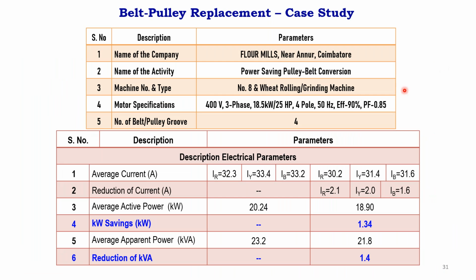This is the simple case study we conducted in a flour mill, which is a wheat rolling mill with a 25 HP motor, which has a 4 belt and 4 groove configuration. This side of the table is the before study, and this is the after study. Before, it took an active power of 20.24 kilowatt, and after changing the belt and pulley with the cogged belt, we achieved a small saving of 1.34 kilowatt, which was recorded for nearly half a day. We took around 4 trials, and I'm presenting only 2 trials. Of course, all 4 trials were at different intervals.